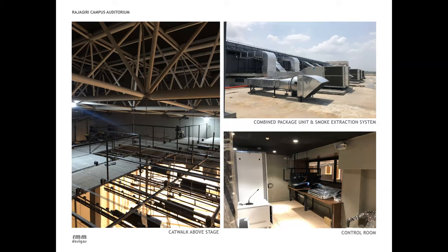Normally what is done is you have a separate exhaust ducting, which you may many a time have seen in the basements of malls or any big buildings, where there is dedicated ducting in the parking area. They pick up the fumes from the parking area and exhaust them out. Here it's a similar principle, but instead of dedicated ducting, we use our return air ducting, which comes back into this unit anyway. Whether it is this unit or a conventional AHU, the principle is the same. Normally the return air comes into the unit, mixes with a little bit of fresh air and is recirculated. When there is a fire alarm, a damper closes the passage into this unit, and the return air gets diverted into this side duct which you see.